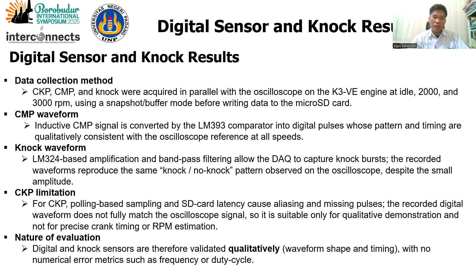However, CKP limitation. For CKP, polling-based sampling and SD card latency cause aliasing and missing pulses. The recorded digital waveform does not fully match the oscilloscope signal, especially at higher speed or higher RPM. Nature of evaluations: digital and knock sensors are therefore validated qualitatively. Waveform shape and timing are mostly the same between the device and the oscilloscope, with no numerical error metrics such as frequency or duty cycle.